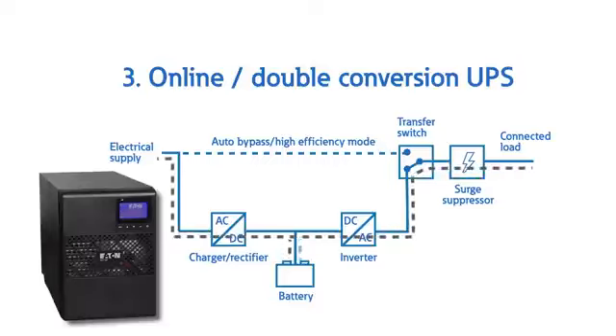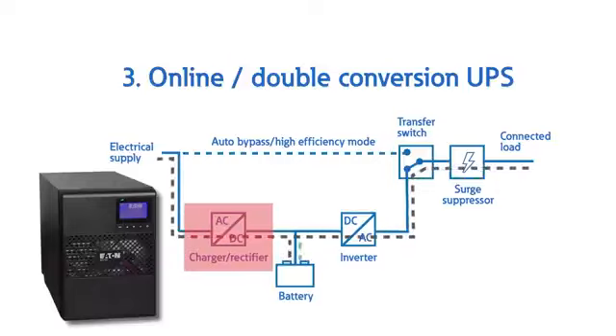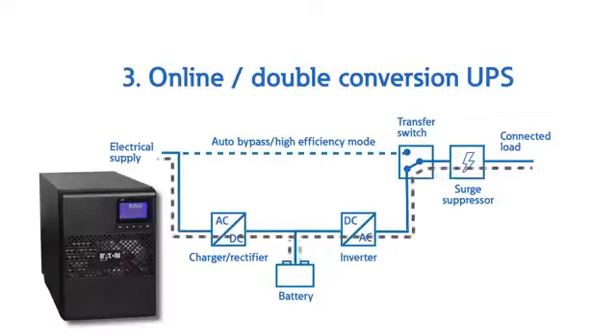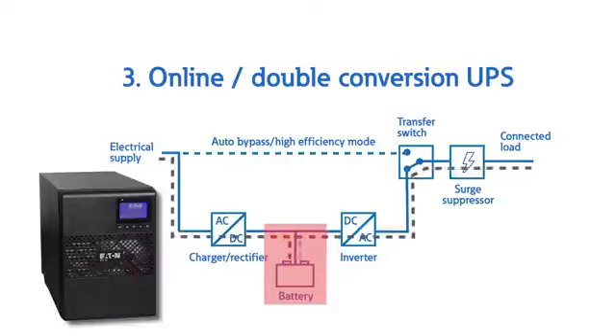Basically, what happens inside a double conversion UPS is the input AC voltage is converted to DC with a rectifier, and then the DC is converted back to a clean sinusoidal 60 Hz AC waveform with an inverter, hence the term double conversion. Like the other two types of UPSs, there's a battery connected to the DC bus, but in this one, the battery charges and discharges without disconnection from the source.